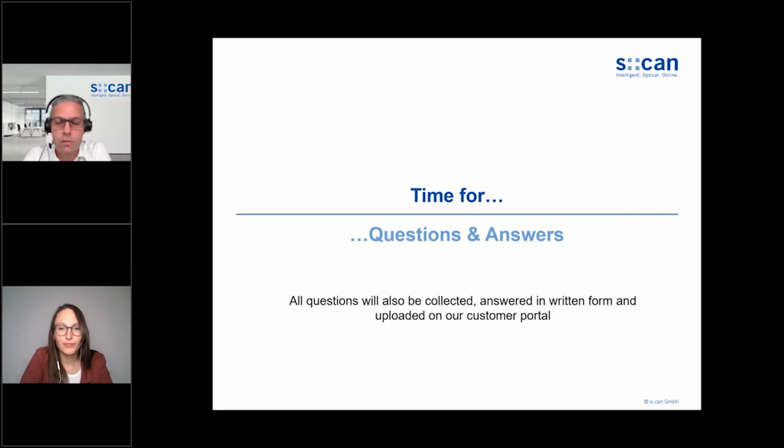And it's nearly always more precise than the laboratory results. So typically, if the customers take 2 or 3 lab samples and analyze them in the lab, the deviation between the lab results is bigger than the deviation from the spectrometer probe. As soon as s::can releases a global calibration, a parameter that is calibrated for a specific application like COD for wastewater, you can be sure that this is well proven in dozens of applications and will work in typical applications.